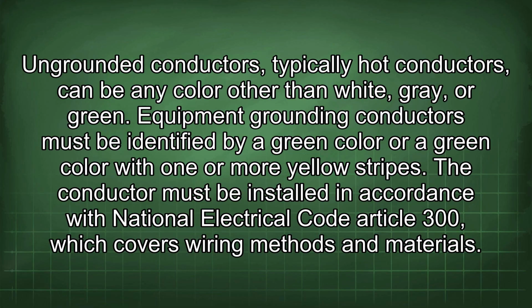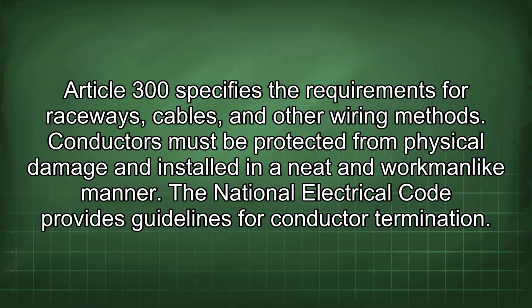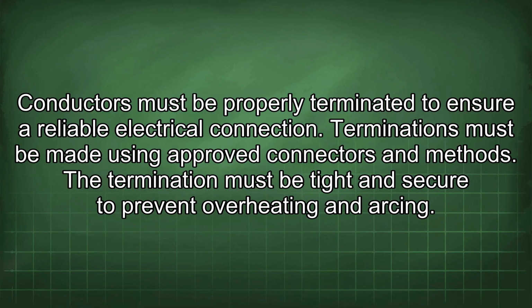The conductor must be installed in accordance with National Electrical Code Article 300, which covers wiring methods and materials. Article 300 specifies the requirements for raceways, cables, and other wiring methods. Conductors must be protected from physical damage and installed in a neat and workmanlike manner. The National Electrical Code provides guidelines for conductor termination. Conductors must be properly terminated to ensure reliable electrical connection. Terminations must be made using approved connectors and methods. Termination must be tight and secure to prevent overheating and arcing.